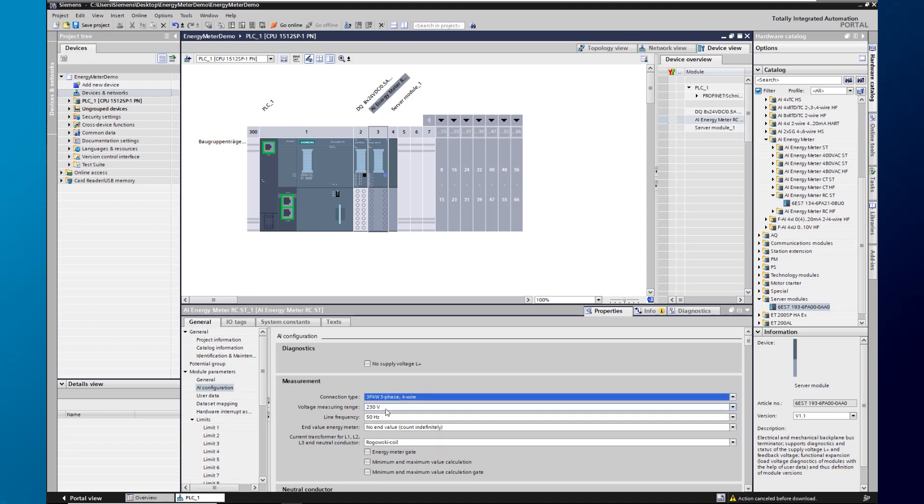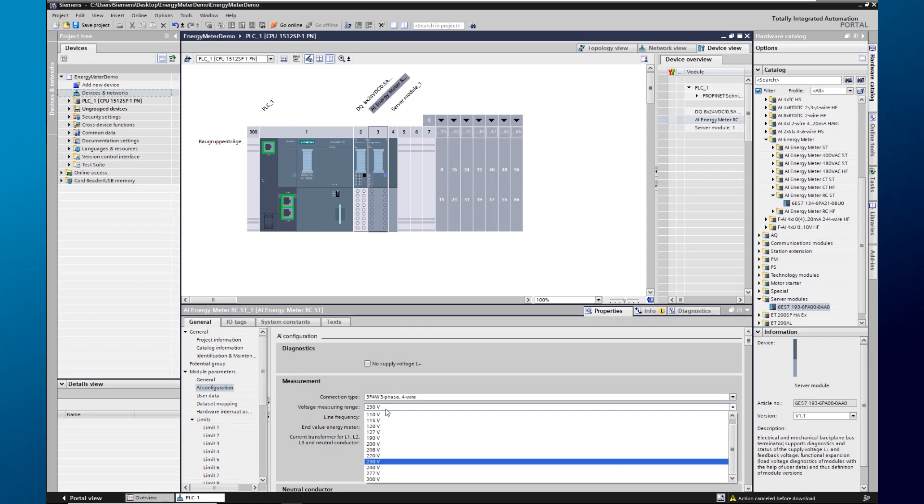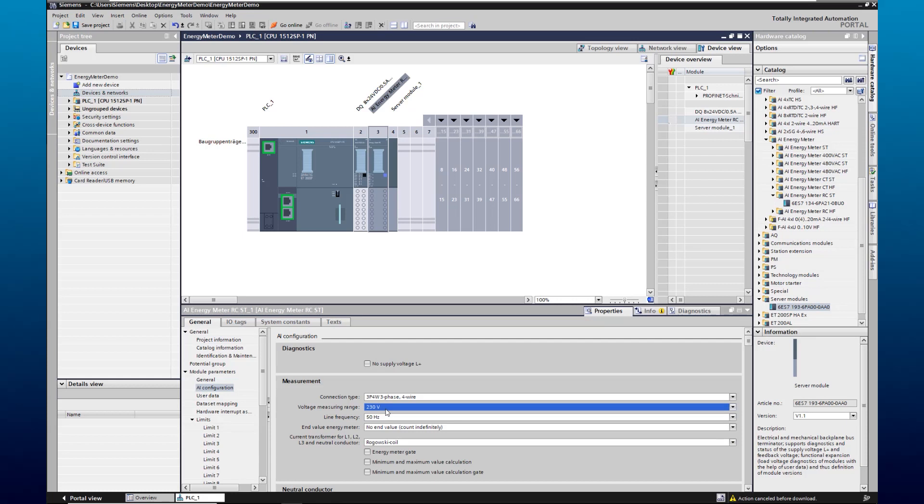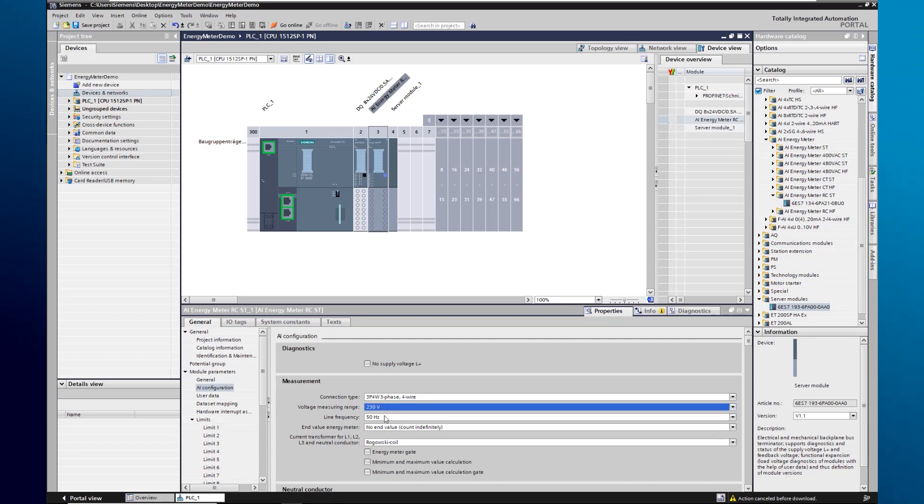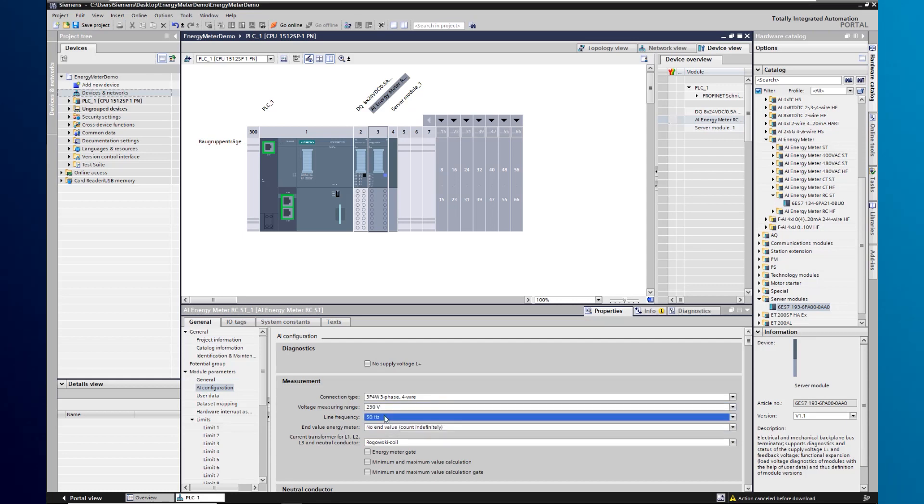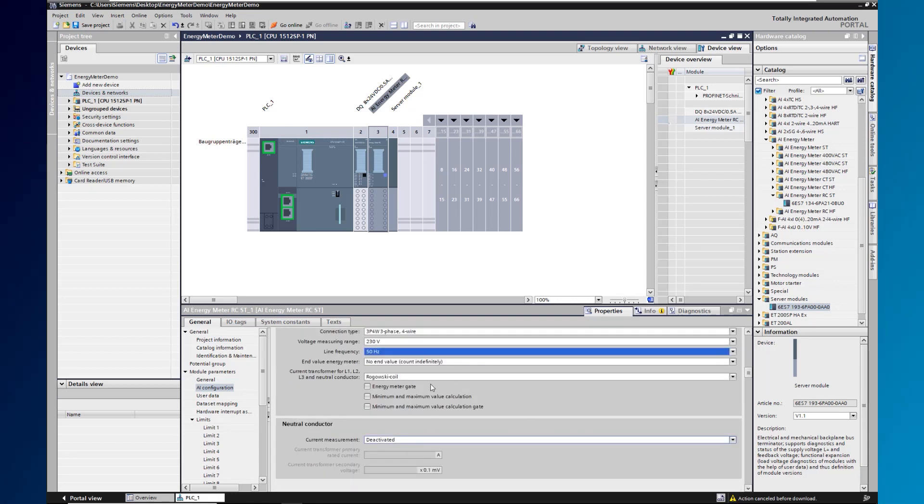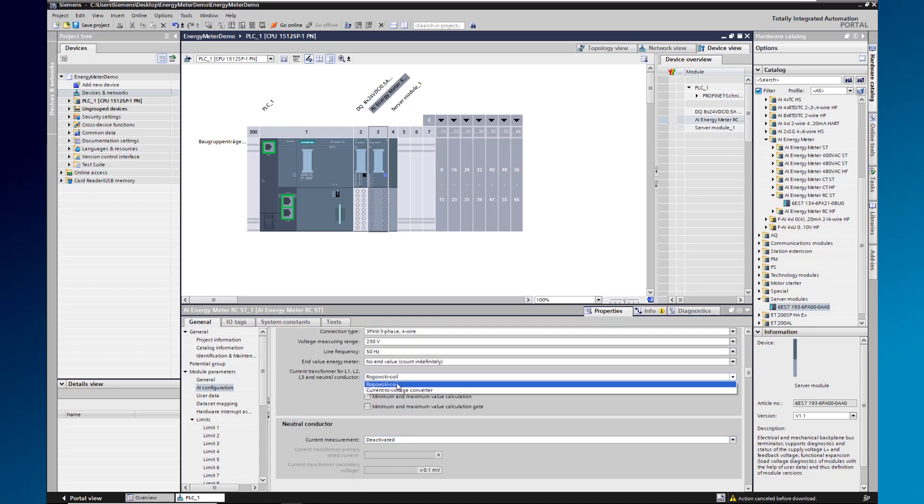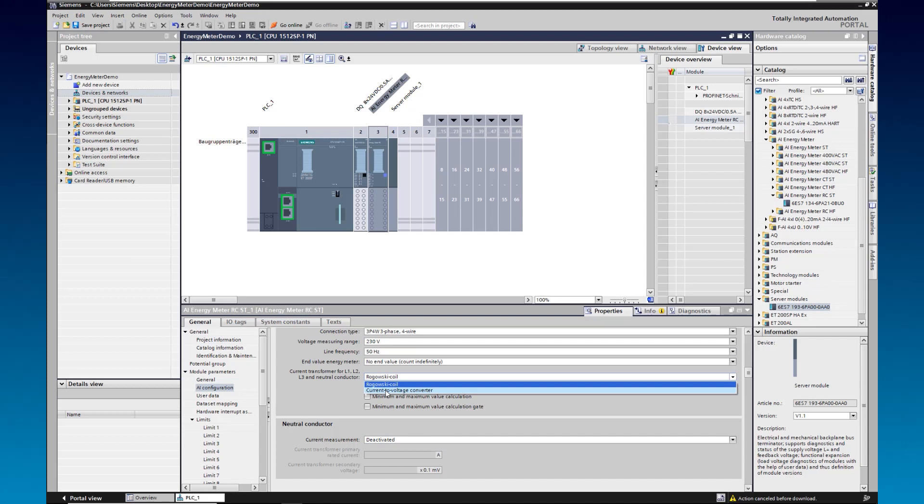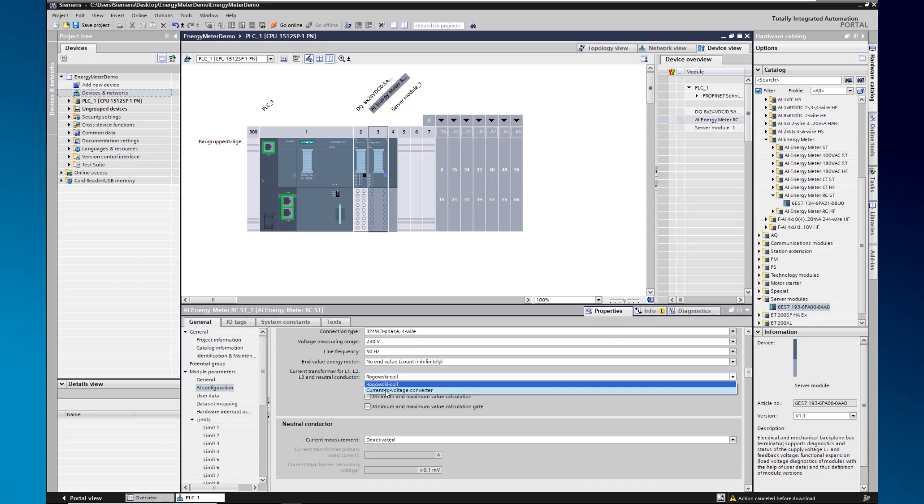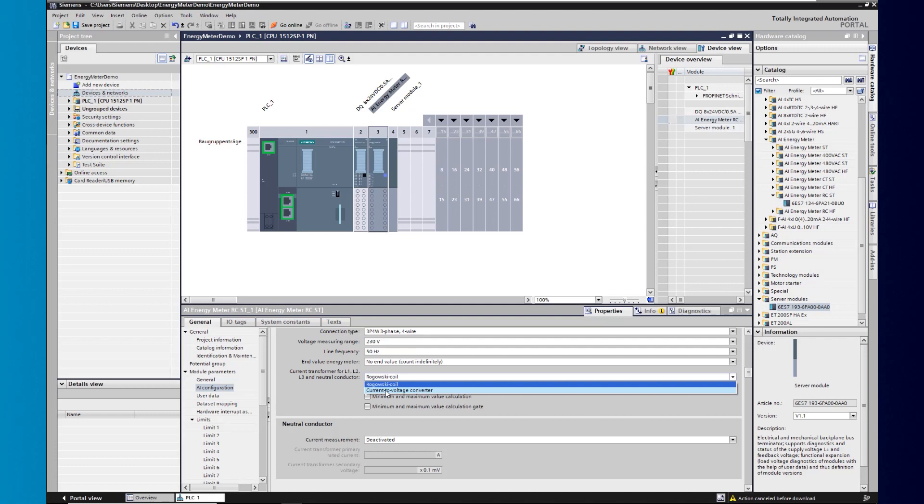Afterwards, we set the measuring voltage and the grid frequency. We also select our transformer type. Since we have chosen an energy meter in the RC variant, we can choose here between the Rogowski coil and the current to voltage converter. In our case, we choose the current to voltage transformer.